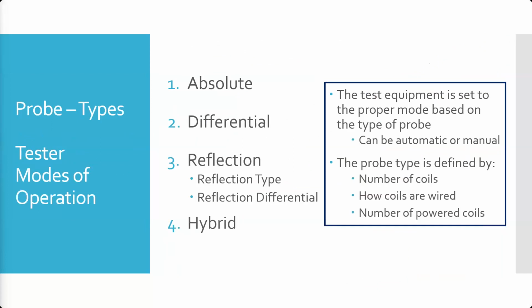The way the probes are operated also plays a role. So there's different probe types. So modes of operation, the 3 common ones are absolute, differential, and reflection. And then a hybrid is a combination of any 2 or more of these. So with our test equipment, the big key is certain probes are designed to work in certain modes. You can set the mode on your test equipment, and if yours is not automatic, which ours aren't, ours are manual, you have to match your setting to the type of probe you're using.